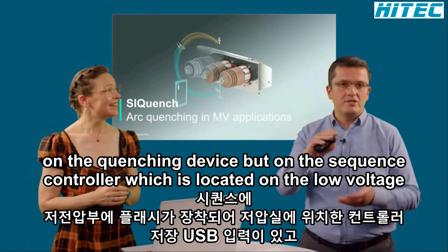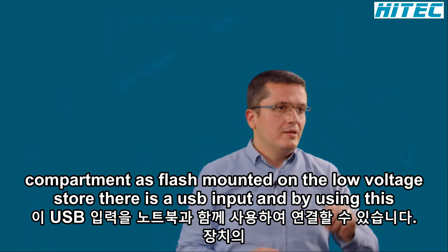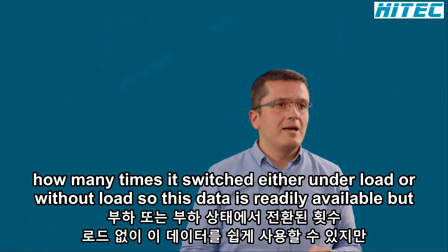Is there an end-of-life indicator on the quenching device? Not physically directly on the quenching device, but on the SIQuench controller, which is located in the low voltage compartment, flash mounted on the low voltage door. There is a USB input, and by using this USB input with your laptop, you can connect to the firmware of the device and read how many times it switched, either under load or without load. So this data is readily available, but in order to access it, you need to get connected.